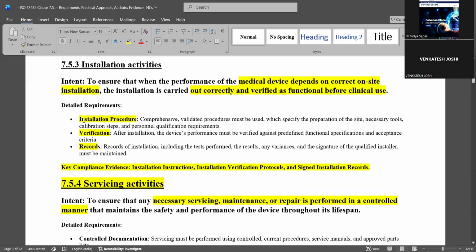Basically, for installation they will have standard procedures, like installation procedures, on how we should do it. A comprehensive validated procedure must be used which specifies the preparation of the site. First, you need to prepare the room where you are installing, and what flooring it should have. There should not be any slope or ups and downs in the flooring. Whether the flooring should be epoxy coated or can be tiles. If you have tiles, what type of tiles you should have, whether granite or normal tiles. All this becomes very, very important.